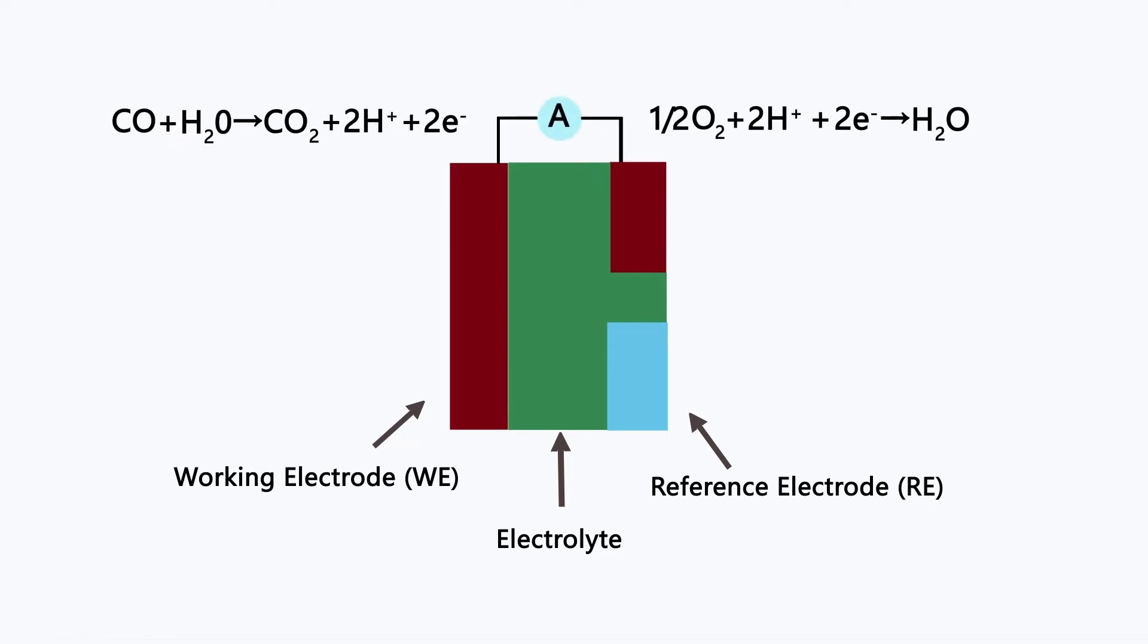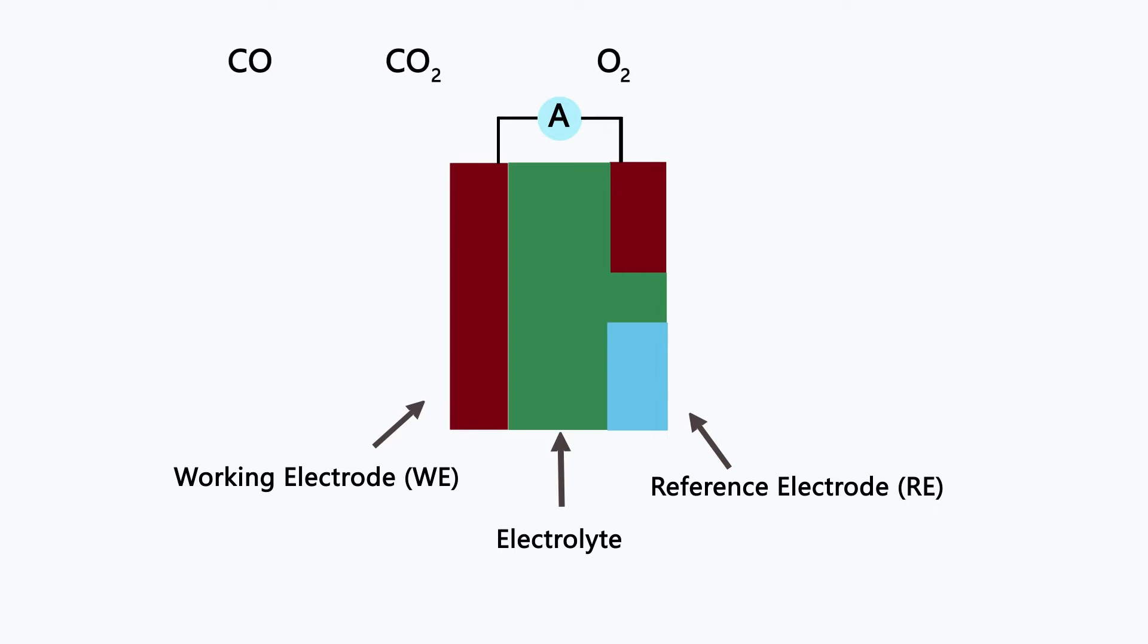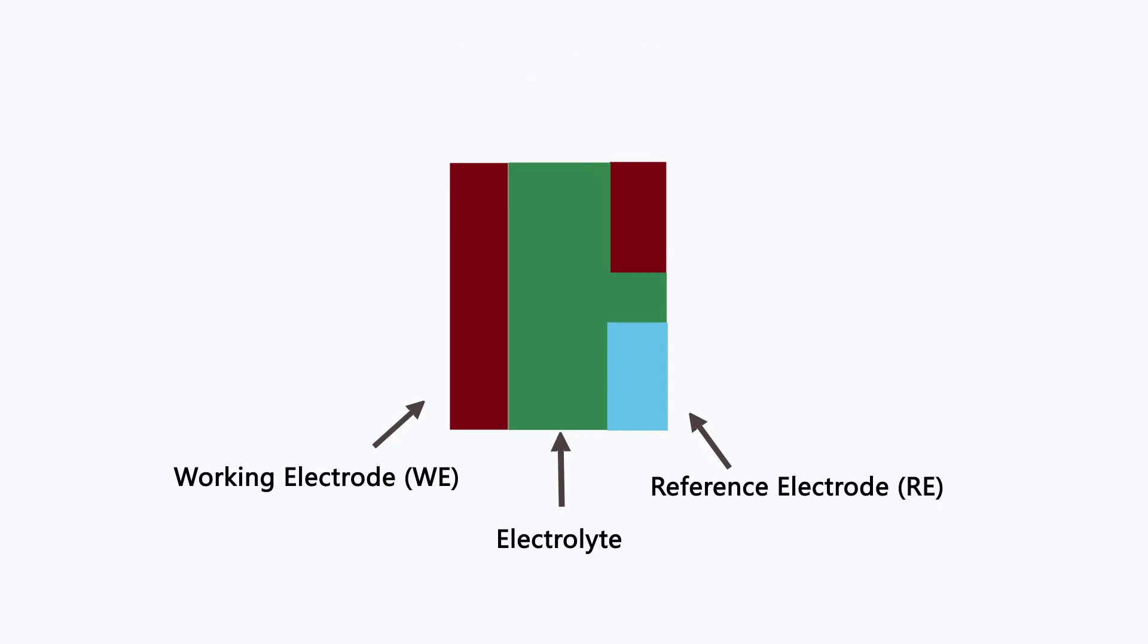The overall reaction is that carbon monoxide is oxidized to produce carbon dioxide. The electron flow forms an external current. The reaction equation shows that the magnitude of the current is directly proportional to the concentration of carbon monoxide.